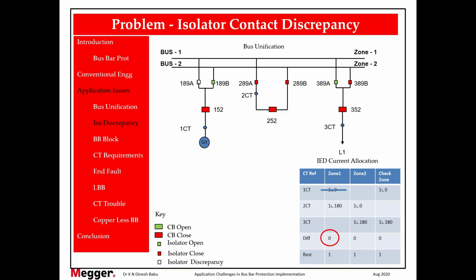Now what should we do? Should we block the bus bar for this condition? We should not block the bus bar. The reason is, if we block the bus bar, then in a worst case scenario, a fault occurring after an isolator discrepancy would not be tripped by the bus bar protection. Therefore, we have to use a secured logic.